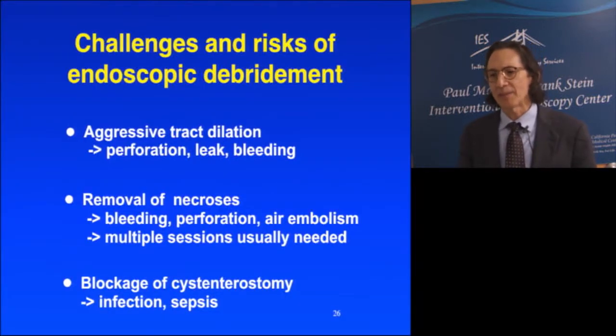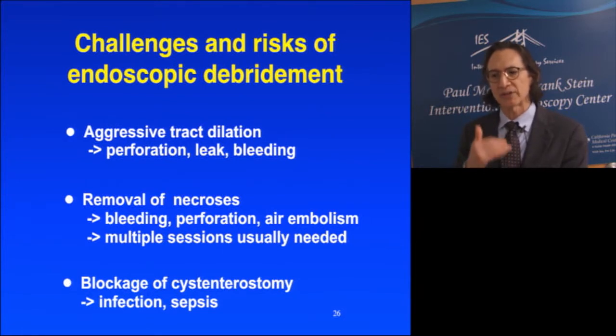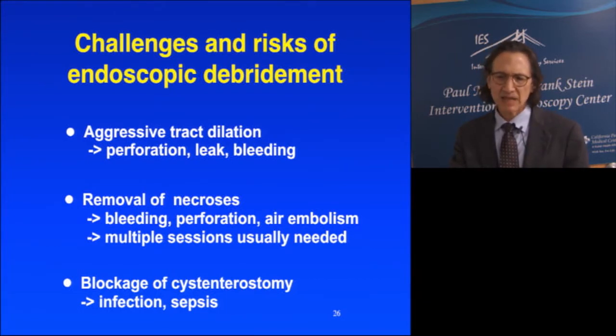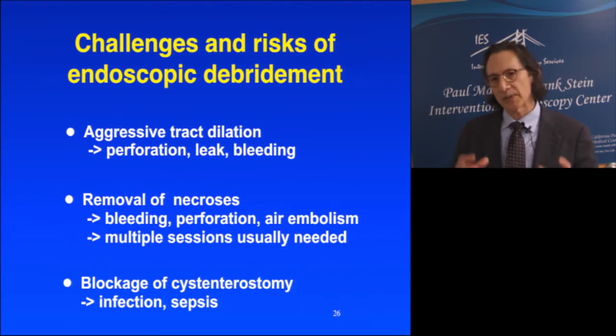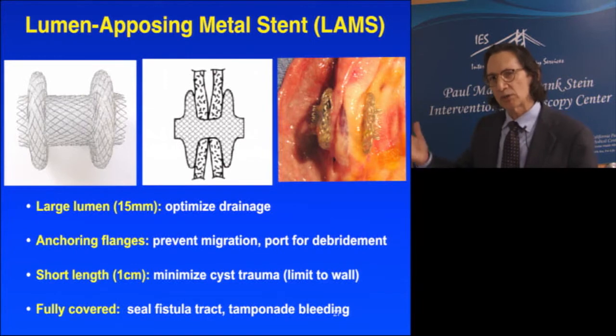This inspired me to develop the Axios stent. The challenges occur at three stages: aggressive tract dilation, which can cause perforation, leak, and bleeding; removal of necrosis, which can lead to bleeding, perforation, and air embolism; and multiple sessions often required. Additionally, the cystenterostomy can close down over plastic stents — initially a large opening collapses, risking infection and sepsis. These challenges at each procedural stage inspired the development of the lumen-apposing metal stent, the Axios stent.